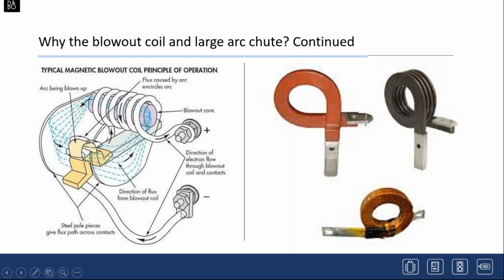Here is a partial circuit of a DC contactor. You have your incoming line coming up, going through the tips, the stationary and movable tips. And this shows the tips opening. And you see an arc here, which is going from the 2 tips. Now the current flows through this part of it, which is called the blowout coil. And the blowout coil actually creates a magnetic field, as shown here, and pushes this arc out into the arc chute. So from whence you get the term blowout, it's literally blowing the arc out magnetically into the arc chute and extinguishing the arc, opening up the DC circuit.